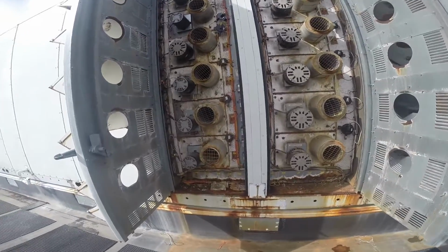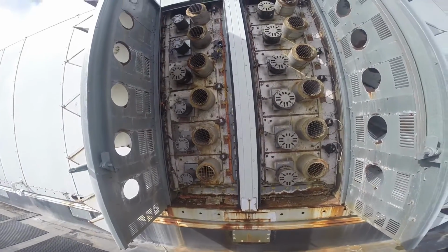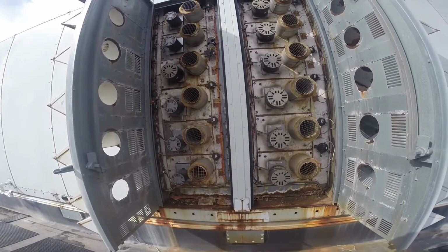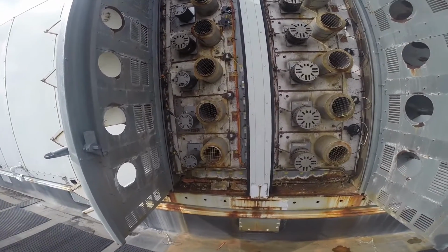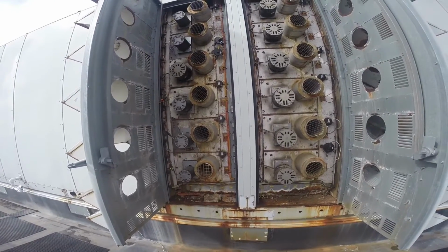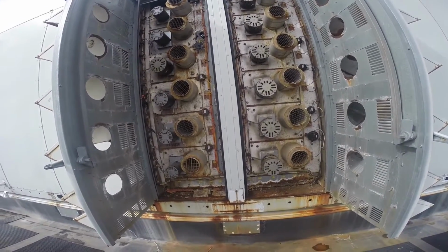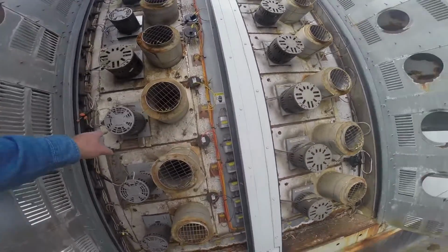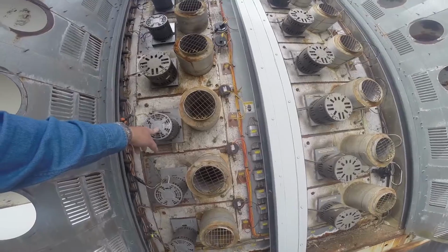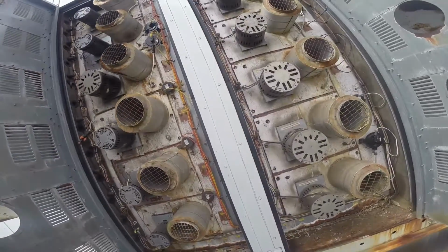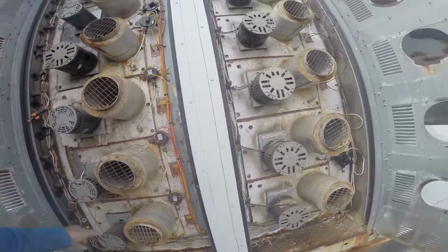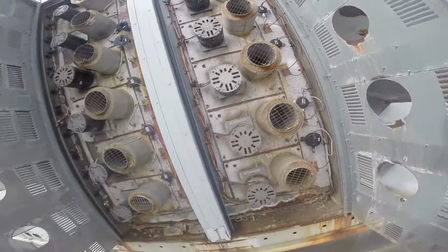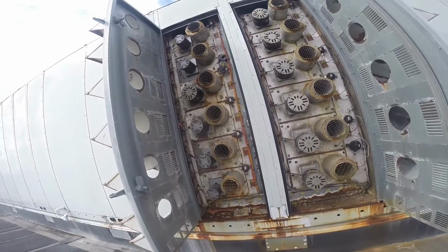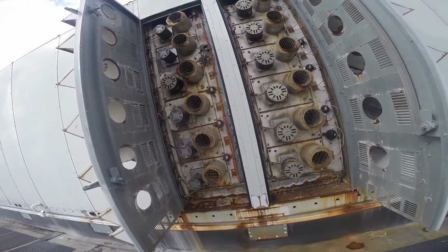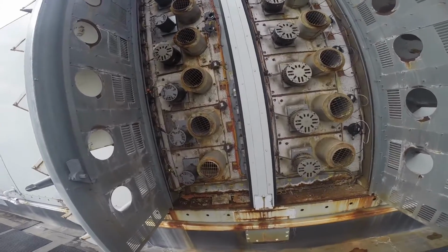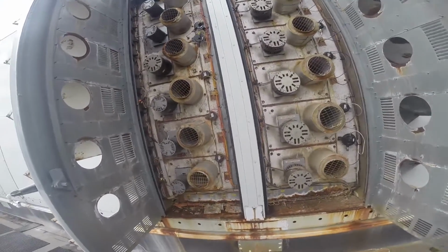Looking at everything over, my advice is just to replace all the heat exchangers. I'm not so sure that I wouldn't replace 1, 2, 3, 4, 5, 6 the induced draft motors. If you look, these would be the newer model induced draft motors, the smaller ones, I believe. And then these bigger ones are the older models. So 1, 2, 3, 4, 5 out of the 12 here have already been replaced. Probably be a good idea to go ahead and change them.